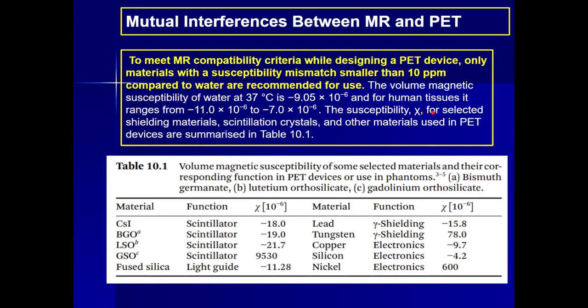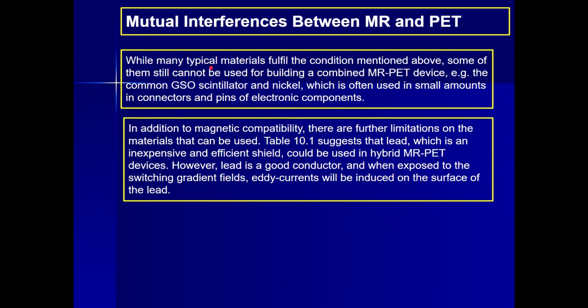The susceptibility for selected shielding materials, scintillation crystals, and other materials used in PET devices are summarized in Table 10.1. While many typical materials fulfill the condition mentioned above, some of them still cannot be used for building combined MR-PET devices. For example, a common GSO scintillator and nickel, which is often used in a small amount in connectors and pins of electronic components.